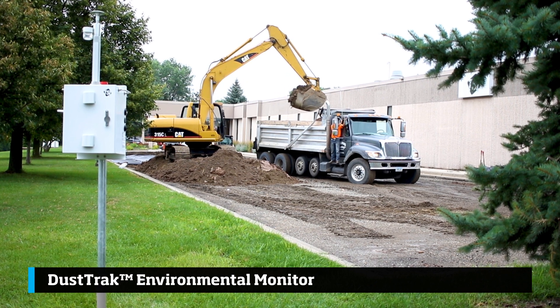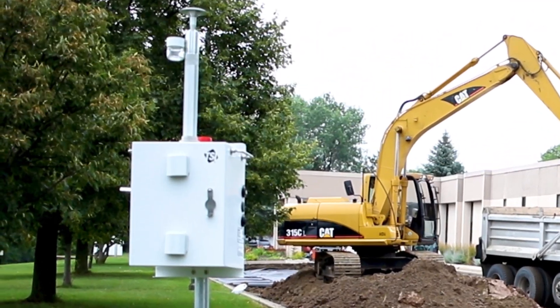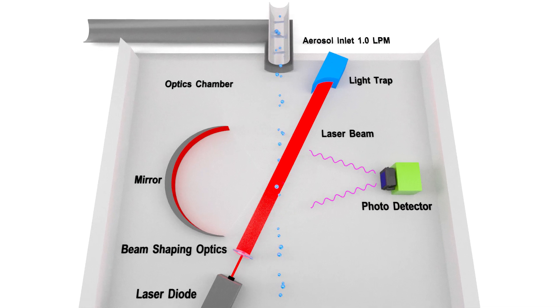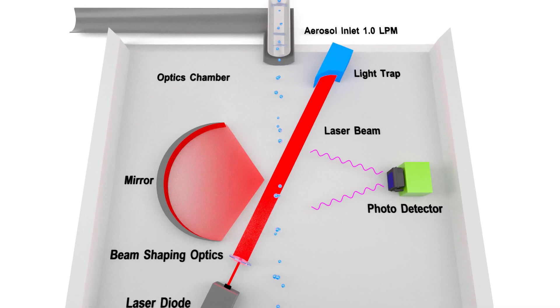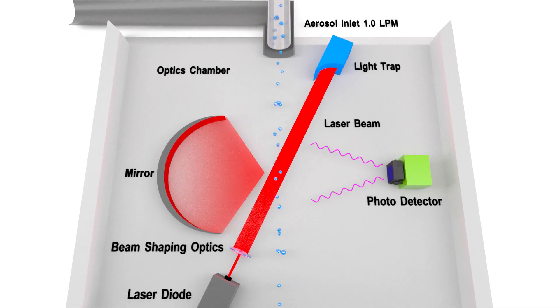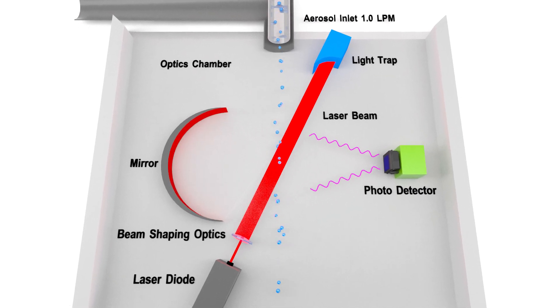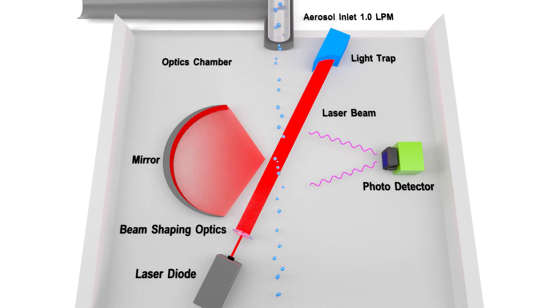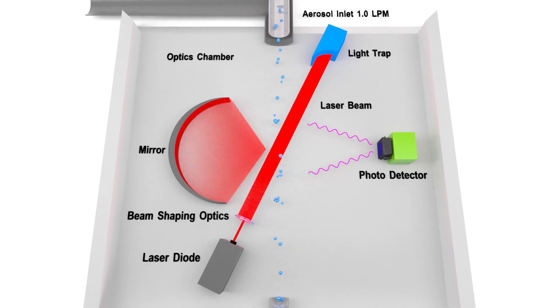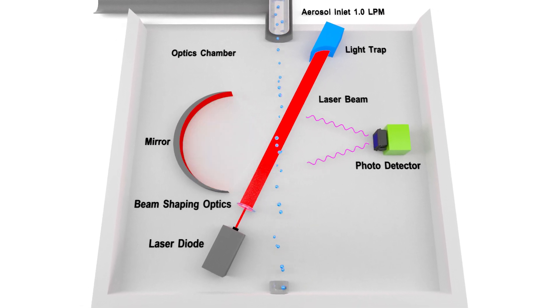At a basic level, the particles are pulled into the instrument through a pump. A laser shines light onto the particles, which creates light scatter. This photometer is used to determine the concentration of the aerosol in milligrams per meter cubed. This type of instrument is widely used in the aerosol monitoring industry, which ultimately helps protect workers and surrounding communities.